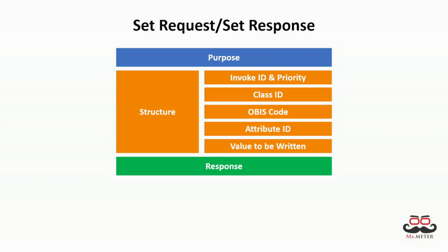The SET request is very similar to the GET request, but the difference is in the response, and the structure you send has a tiny difference. In the structure you send, after the attribute ID, you have to provide the value to be written to the object you want. And based on the object, the value and its format are completely different. You can read them in the Green Book, which has very extensive knowledge in there.